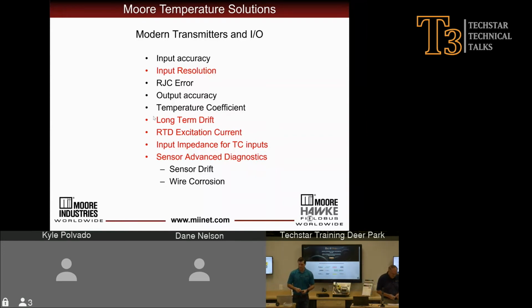So input impedance for thermocouple inputs. And then sensor advanced diagnostics as well. So looking at different features such as sensor drift over time, wire corrosion, broken wire detection, all of those things might be important in selecting the correct transmitter when you're measuring a high temperature or high accuracy temperature process.